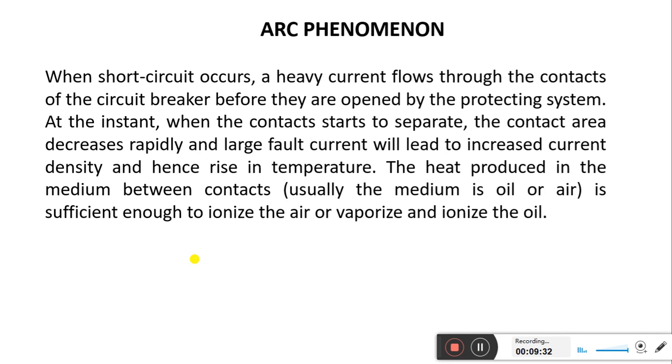So what is the arc phenomenon? When a short circuit occurs, a heavy current flows through the contacts of the circuit breaker before they are opened by the protective system. At the instant when contacts start to separate, the contact area decreases rapidly, and a large fault current will lead to increased current density and hence a rise in temperature.